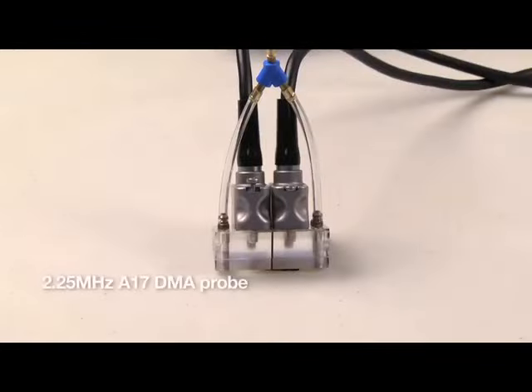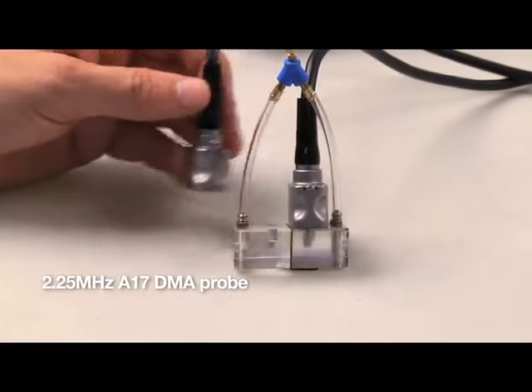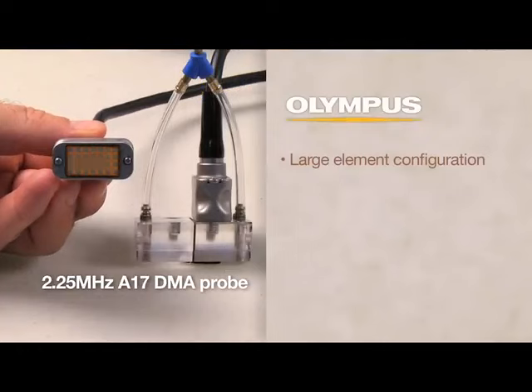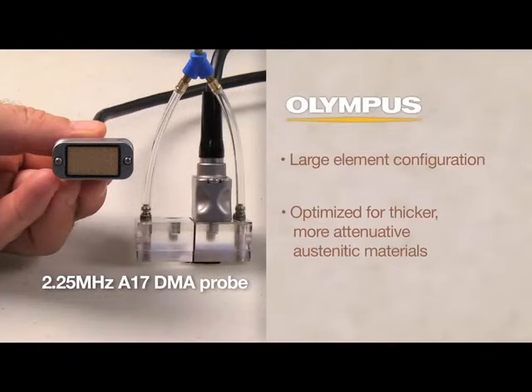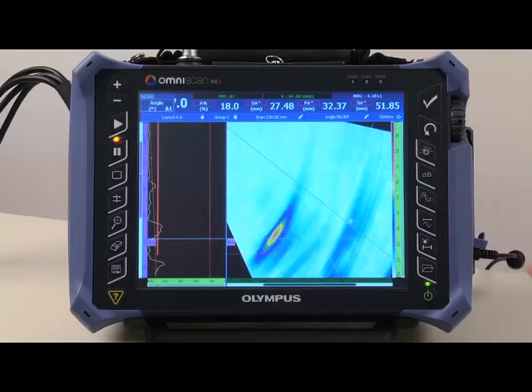The Olympus 2.25 MHz A17 DMA probe contains a 4x7 large element configuration in each housing optimized for thicker and more attenuative austenitic materials.